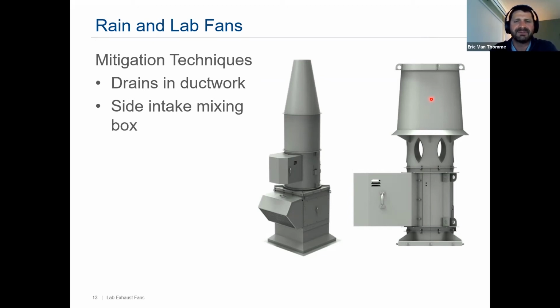If you have an N+1 type application where you've got some staging and you've got one fan shut down for a period of time, rain can actually make its way through the fan down into the ductwork and ultimately down into the building space if certain mitigation is not taken. So there's really two ways to handle this with this inline style fan. One would be installing drains in the ductwork, which is pretty common. We've seen that quite a bit to capture the rain in the ductwork and then run drains off of that so it doesn't get down into the space.